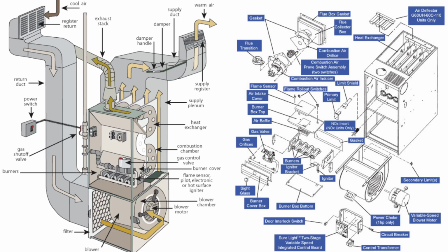You now have your flame sensor, your pilot assembly, your electronic or hot surface gas igniter within that location. That's where everything is, basically your combustion area, and then above that is your combustion chamber. As you go above that, you'll see the heat exchanger. That's where the gas heats it, surrounded by air, and the blower assembly, when it is in operation, will pick up and absorb the heat and move it. You have your supply plenum. On this one, it has a supply plenum, which it will feed up into. It will either have a damper in it where you can control the flow. You can have a damper handle on the supply duct itself, which is galvanized in this one, and then your supply register, and that's basically where it comes up.